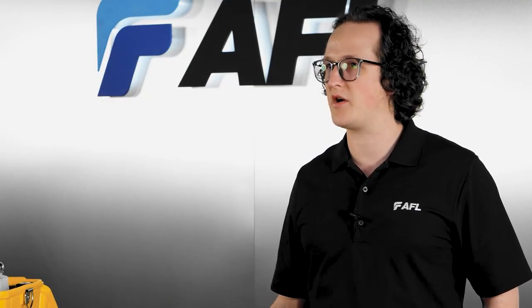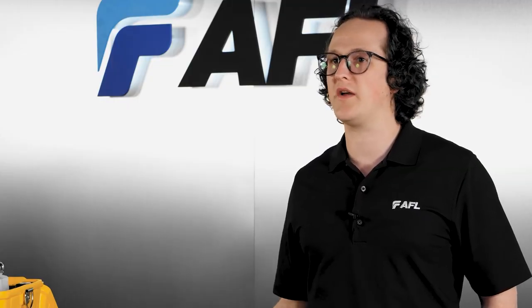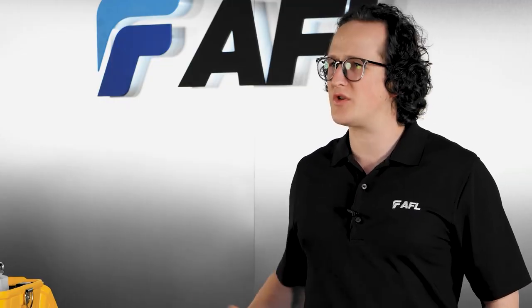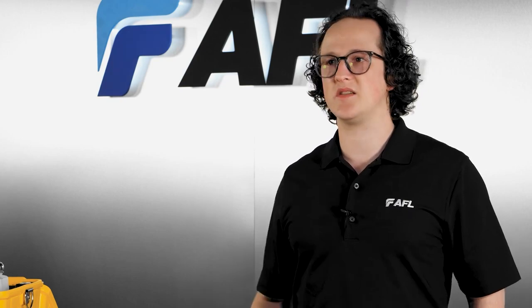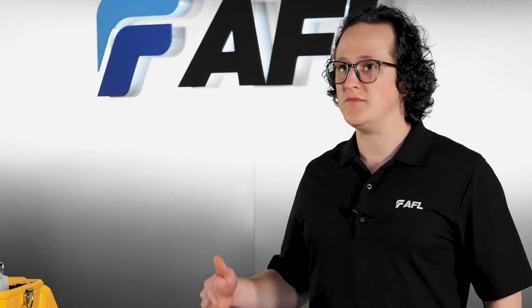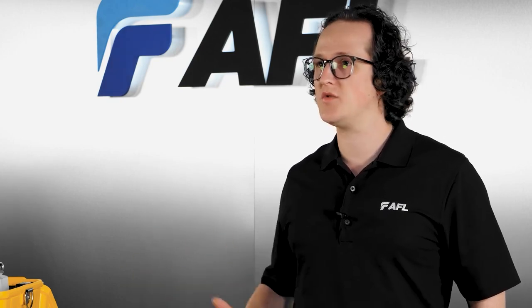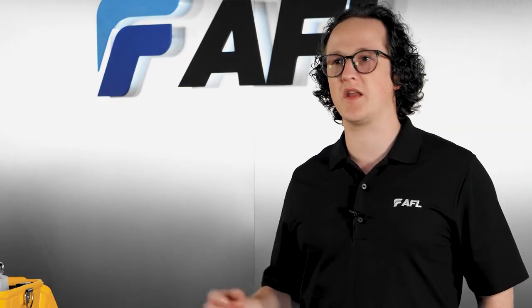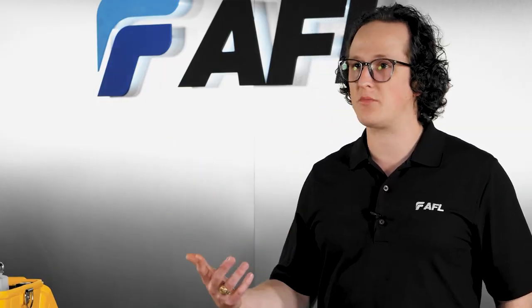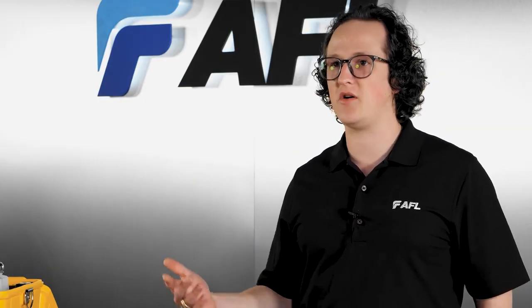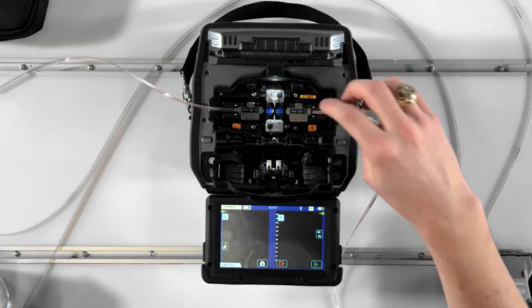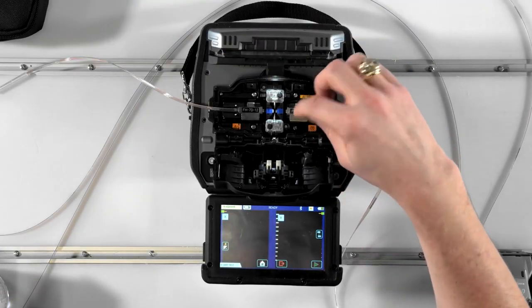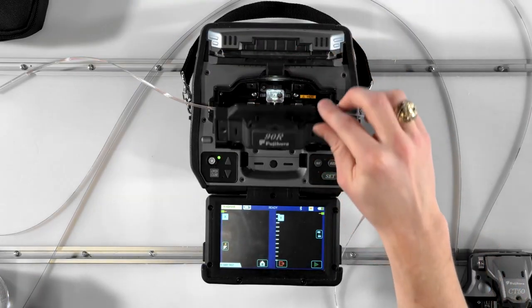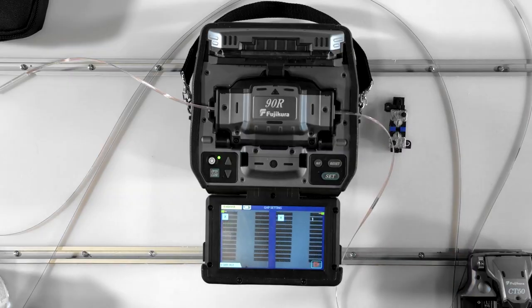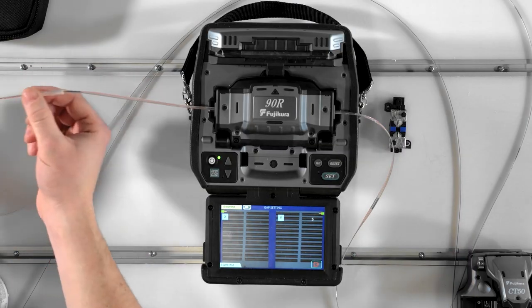Conditions like temperature, barometric pressure, and humidity all affect how much arc power you need in order to precisely melt the fibers. And since every day has different conditions, start the day with a quick arc calibration to get you started, then use the splice mode ending in auto to keep the initial calibration accurate as the conditions of the day evolve. Any splice mode that has the fast suffix will assume the correct fiber type is loaded, the correct number of fibers are loaded, and adopt the most recently calibrated arc power value in order to perform the splice in as little time as possible.